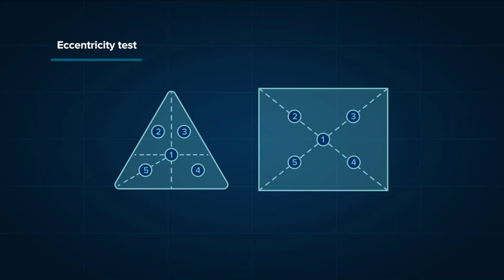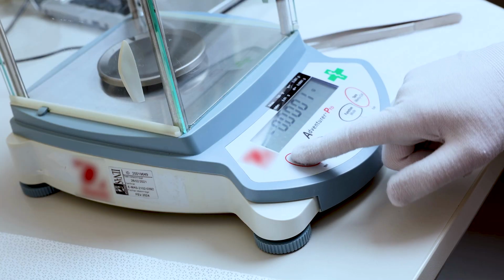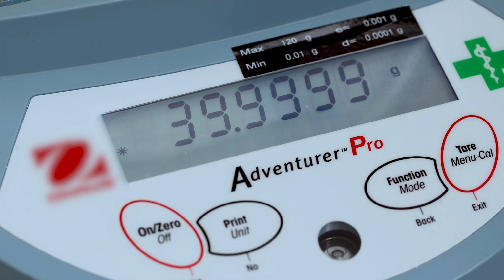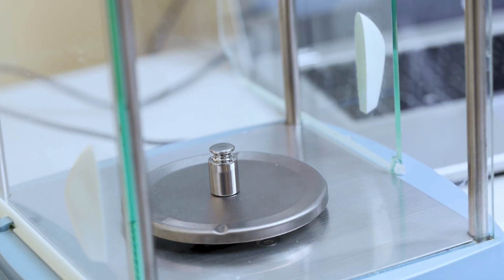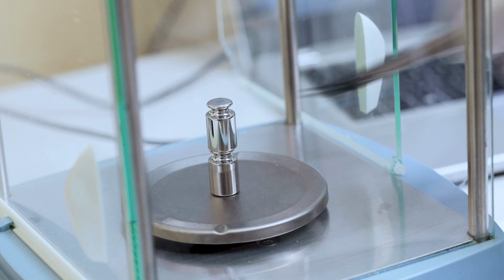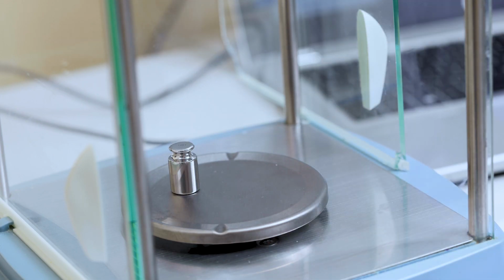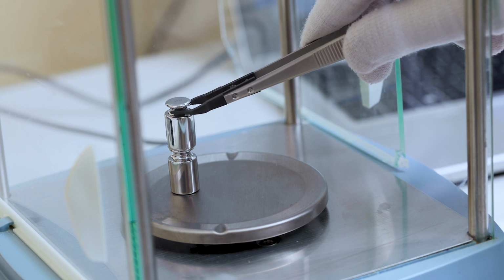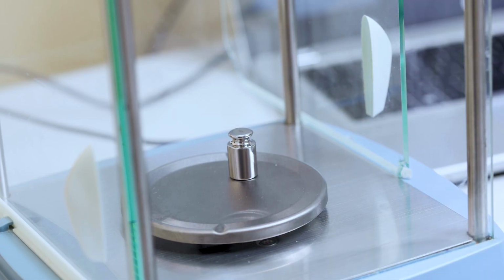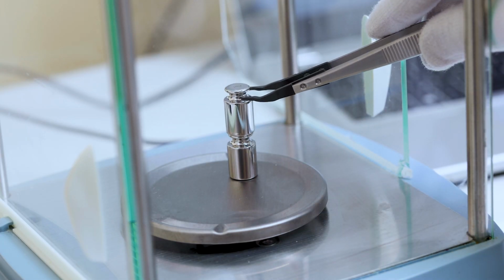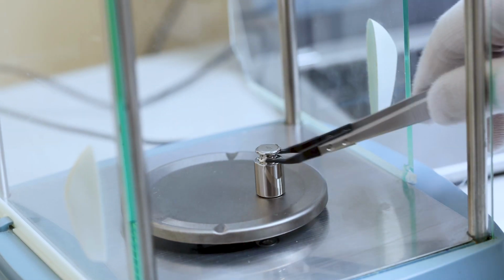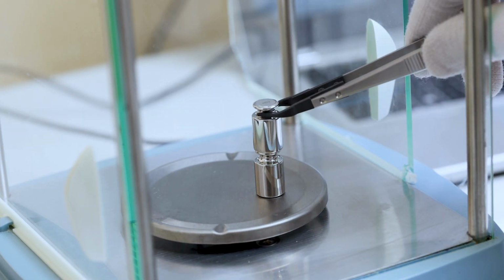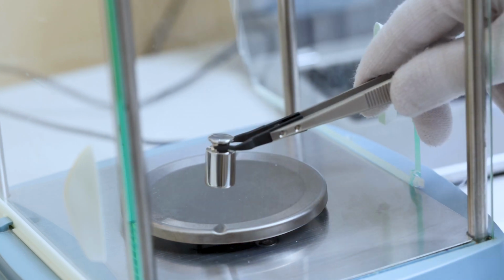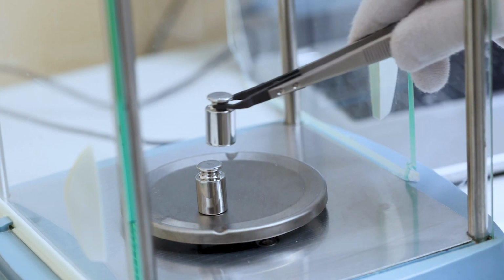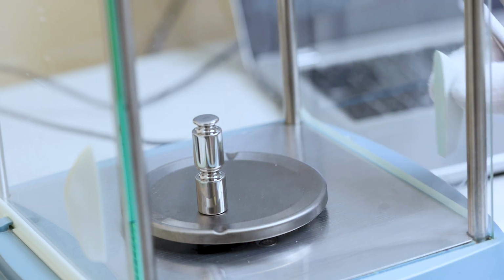The next step is to carry out an eccentricity test. For this purpose, the operator uses a weight with a value of 1/3 of the maximum capacity. First, he places it in the middle. In a second step, on the 4 sides of the weighing plate at well-defined points. It is recommended to carry out this eccentricity test on a half measure between a corner and the middle of the plate. The determination of the eccentricity allows us to define if the measure is carried out in a homogeneous manner over the entire surface of the plate. It can be omitted depending on the customer's use of the scale.